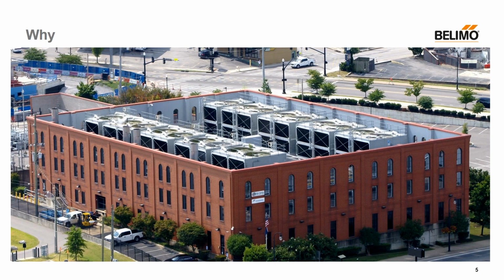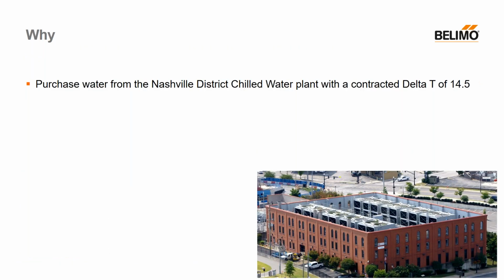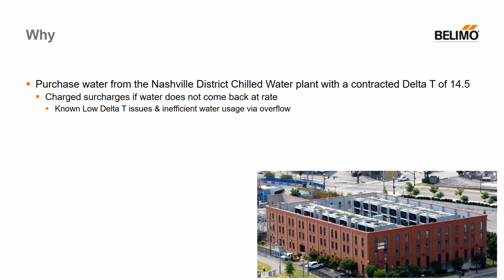The Nashville District Chilled Water Plant that you see pictured here is a massive complex down on the river near downtown Nashville, and it serves around 50 buildings throughout downtown Nashville. Each of their customers has a contracted delta T rate. If those customers do not meet that contracted delta T, they're hit with a monthly thermal inefficiency surcharge. In JLL's case, their contracted rate was for a delta T of 14, but they were returning a delta T that averaged between 4 and 6 degrees. Therefore, they were paying a thermal inefficiency surcharge that reached $12,000 to $13,000 per month during the peak months.